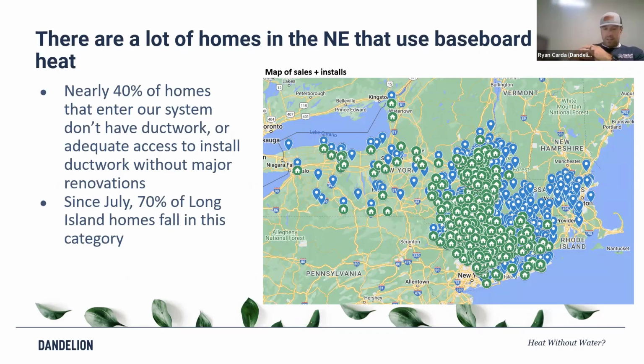Our approach is entirely forced air heating and cooling, so before the VRF addition to our catalog, we typically only installed packaged or split equipment. But with all these digital leads coming in through that survey process, we find a very big percentage of the homes entering our system are heated with boiler-fed baseboard radiators. A lot of those homes either don't have ductwork and don't have AC at all, or they have what we refer to as AC-only ductwork, potentially put in as an afterthought after the house was already built.